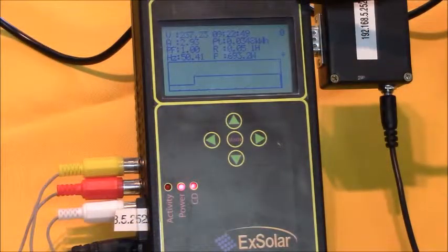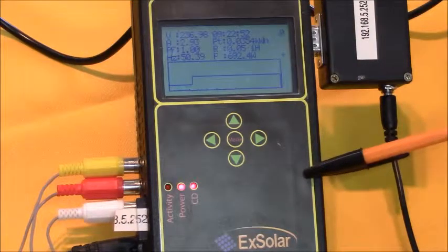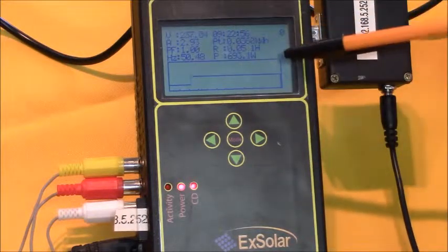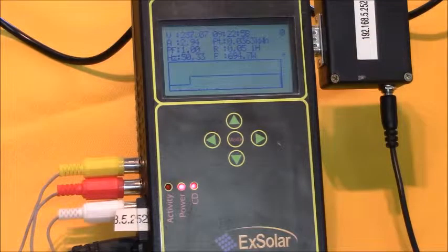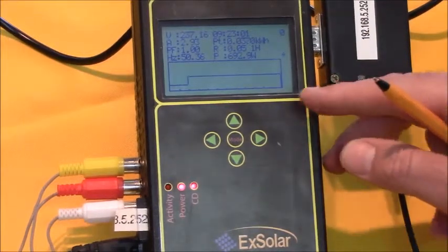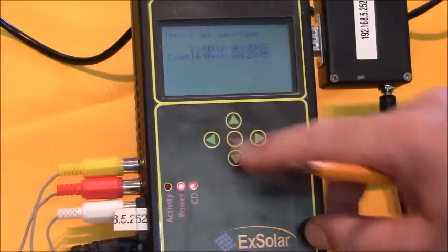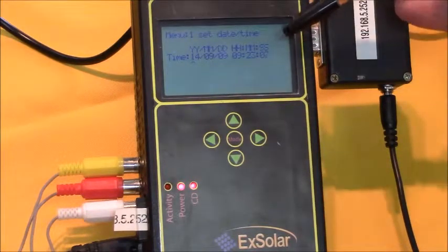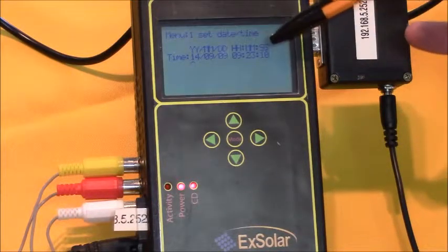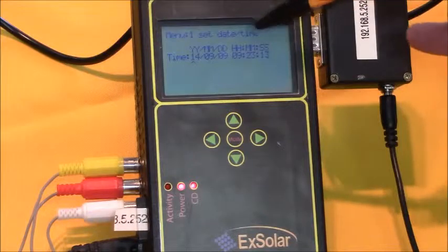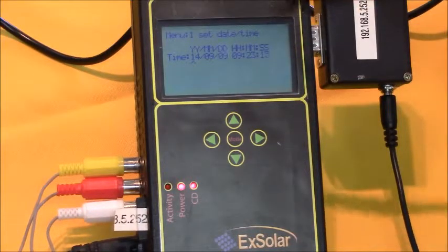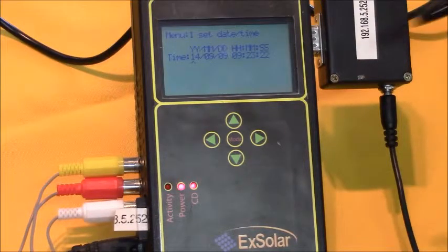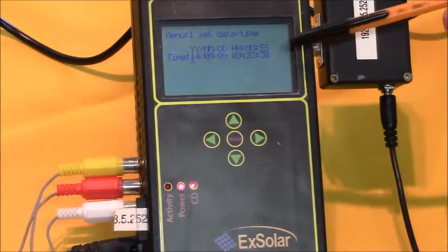Here is a zoomed in picture of the ExSolar EM502 and the initial screen which comes up. For the first part of the calibration, if you push mode, you go to the time and date screen. On board there's a real-time clock, and it's important that this is within a few seconds of the actual time, because when the data is sent through via the Wi-Fi module to our server, if you want to see live data and the reaction as you turn an air conditioner on or something like that, you want the time as close to real time as possible.